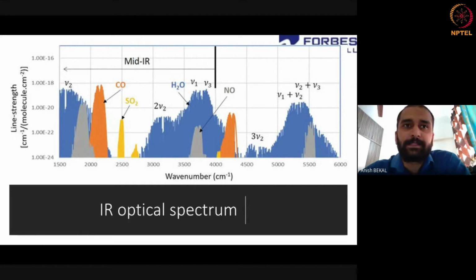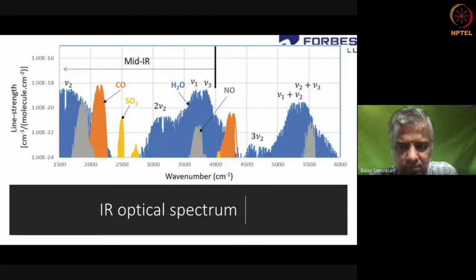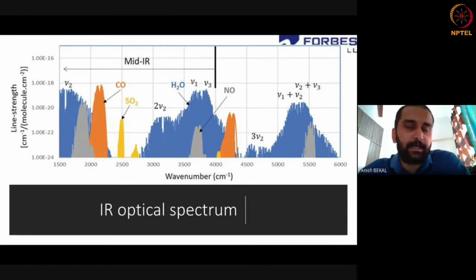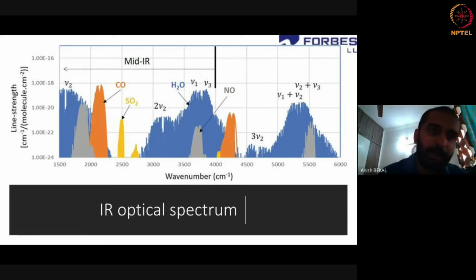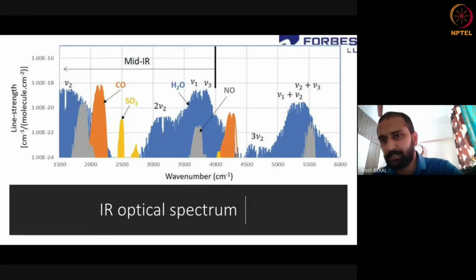So there have been several cases of wrong reporting. They basically send out a notice to shut down the plant if the pollution is above the limit, and it's a legal thing to shut down the plant when they send notice. So they have made it mandatory that all the data from the instrument has to go directly to their server. It cannot be routed through any of the computers where manipulation can be done. So that has now become mandatory. It is not good to have, it is a mandatory thing.